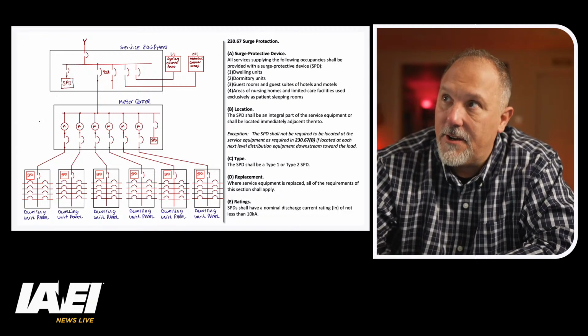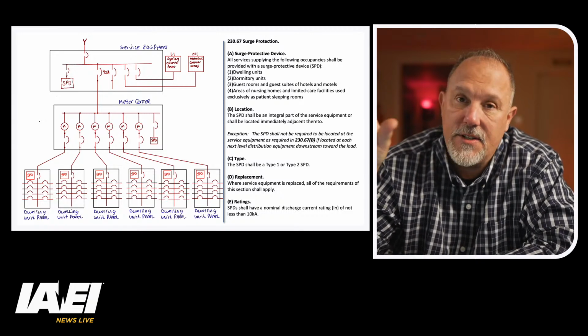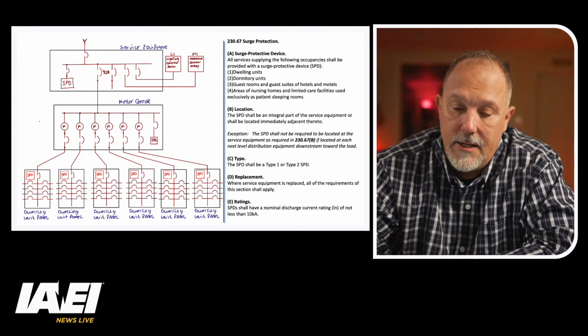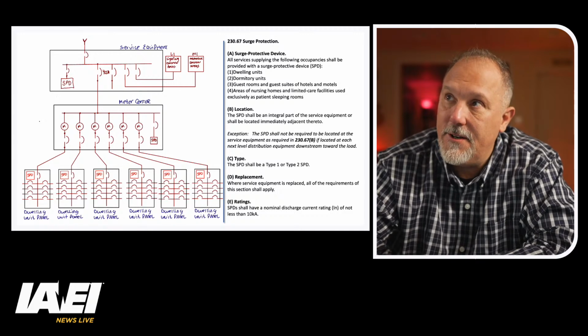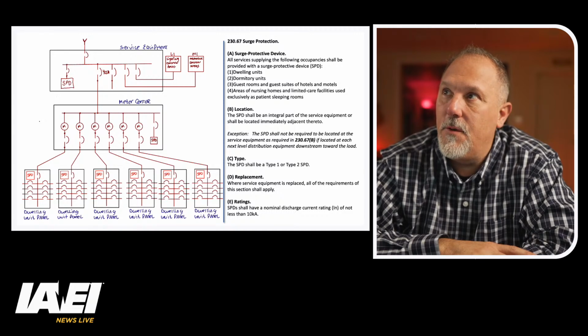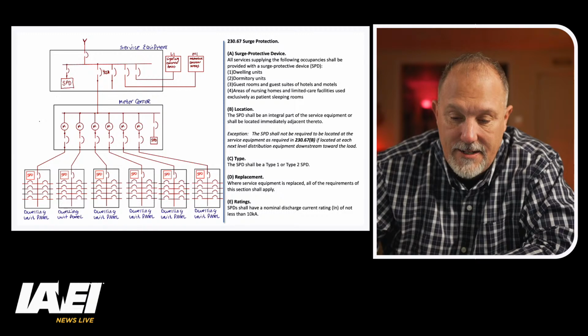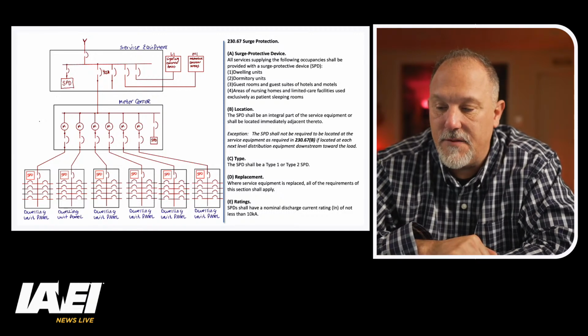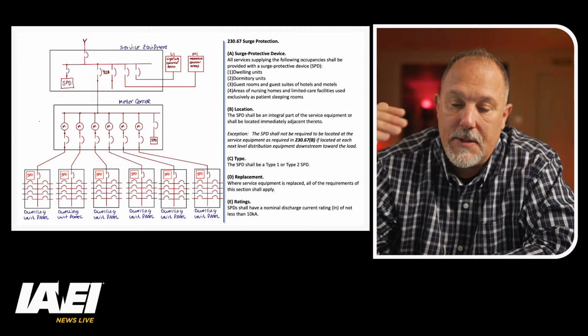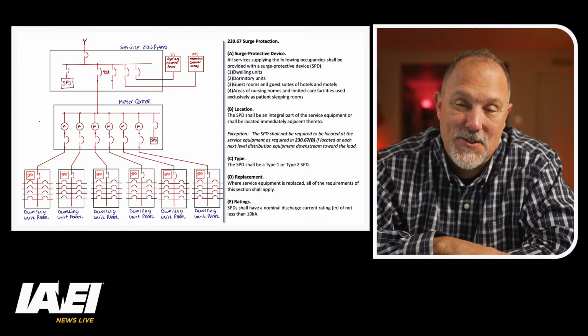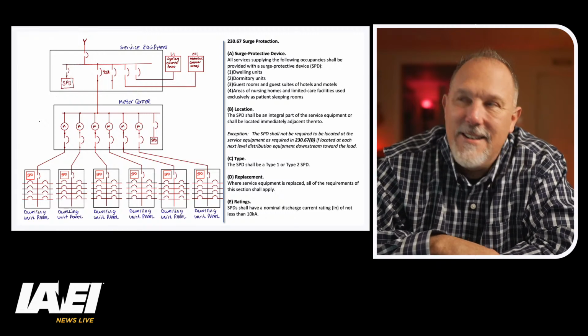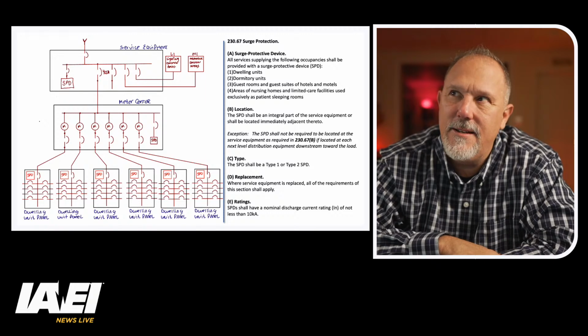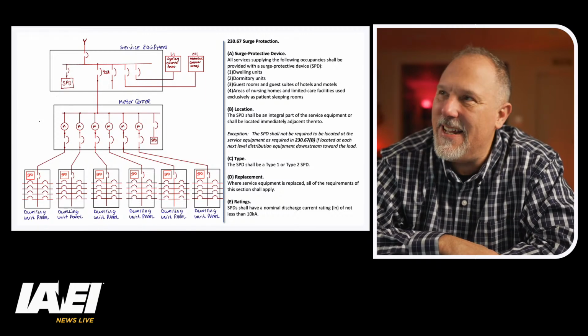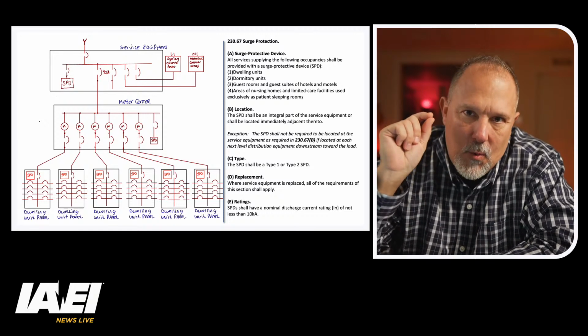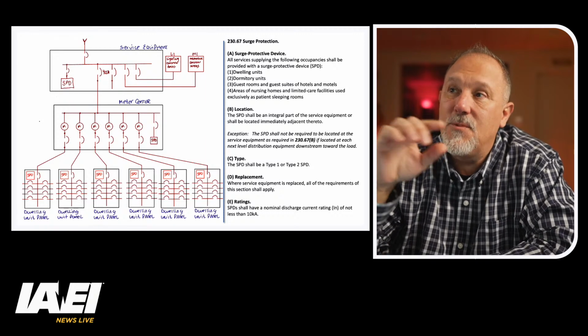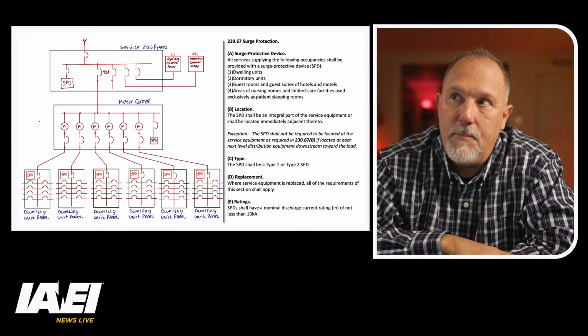So now the meter center is not covered by Article 230 because that's not service equipment. The meter center is actually feeder equipment at the end of a feeder. So the rules you would follow for the feeder that supplies the meter center are in 215, and it says where a feeder supplies any of the following, a surge-protective device shall be installed. So if that feeder that feeds the meter center supplies a dwelling unit, which it does, and I had to call a few inspectors on this one, and I remember Donnie Cook telling me, he says, Thomas, if you remove that feeder, do those dwelling units get power? And I said, no. He goes, well, then that feeder supplies the dwelling units. I'm like, man, okay. So that meter center would be required based on 215 to include surge, as well as each of those dwelling unit panels, based upon the language.